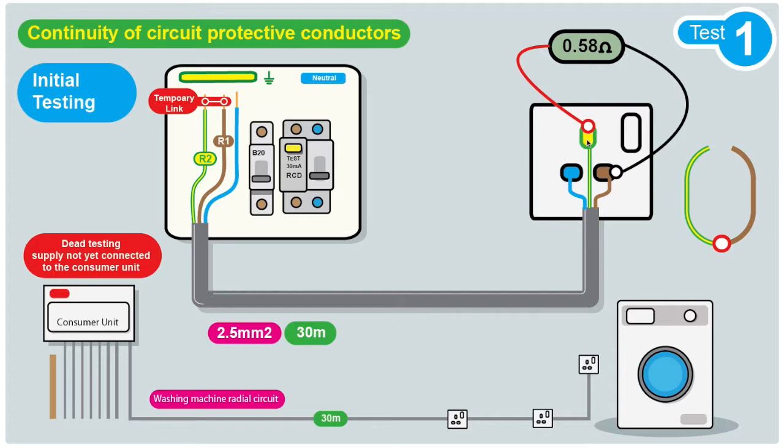The CPC at the furthest point. Now we put a temporary link between the CPC and the line cable, then we go to each point and test between the CPC and the line cable conductor with a test meter.